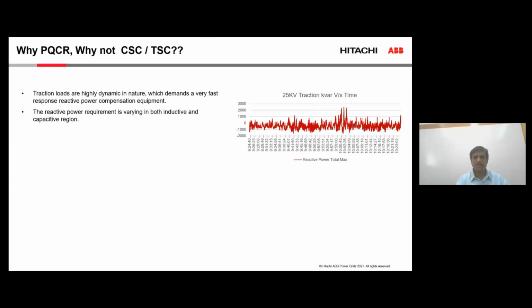Then the reactive power: if you take a metro, for example, it requires sometimes capacitive power and sometimes it requires inductive power, to correct the reactive balance. When the traction is the main load, then we need capacitive support. And when it is a light load condition, it's only the cables that are in the picture. Then we need inductive power to be given to cancel the cable. So we sometimes require capacitive, sometimes we require inductive, in order to maintain the power quality of the system. Which means we need a system that can give both inductive as well as capacitive.